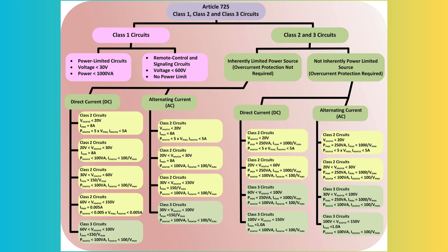Class II and Class III circuit conductors are not required to be installed in the raceway. Class II or Class III circuit conductors cannot be installed in the enclosure, raceway, or cable with power or Class I conductors unless they are reclassified as Class I circuits. Class II and Class III circuits can be installed with Class I, non-power limited fire alarm, and medium-power network-powered broadband communication circuits, but only if they are separated by a barrier. When Class II and Class III circuit conductors are mixed, the wiring methods for Class III circuits must be followed.